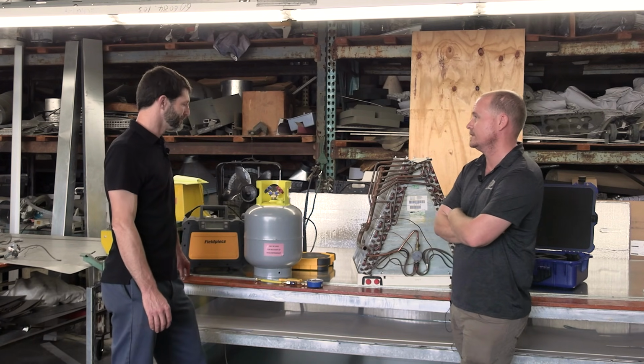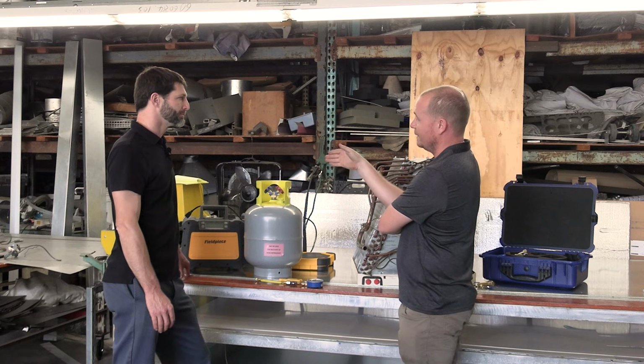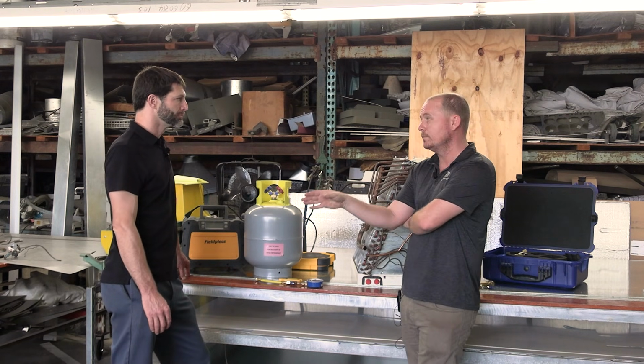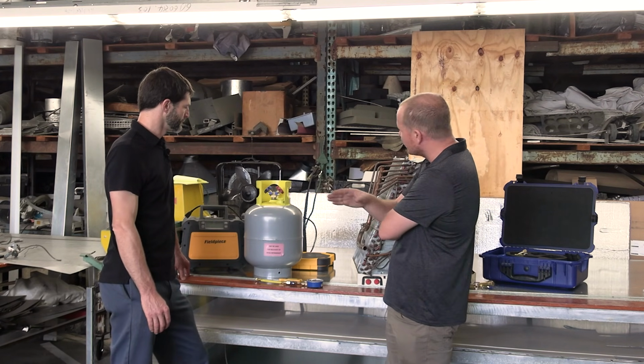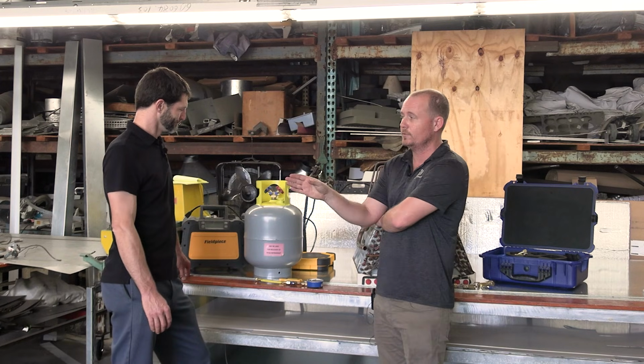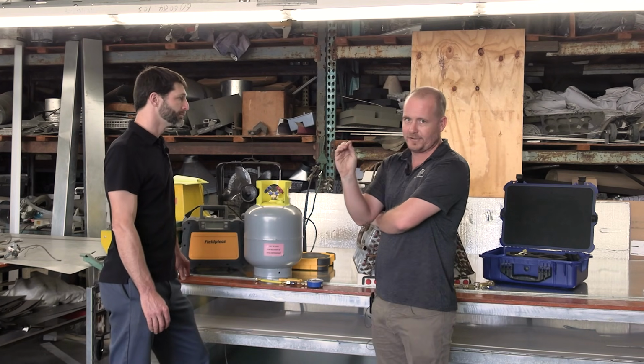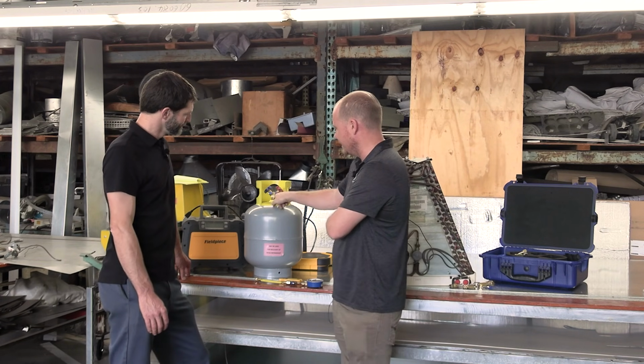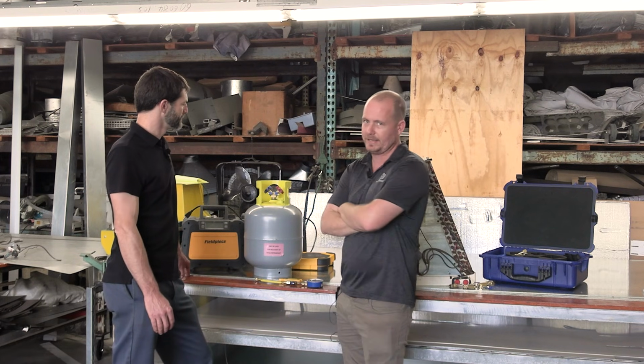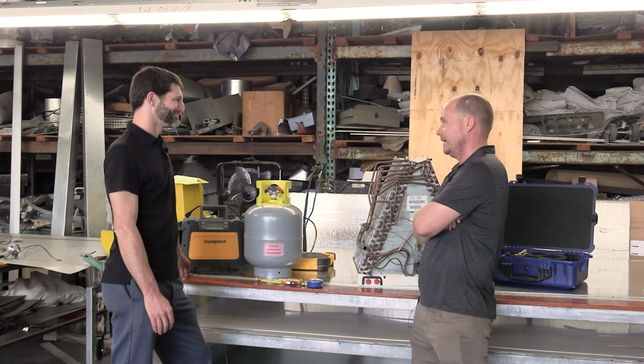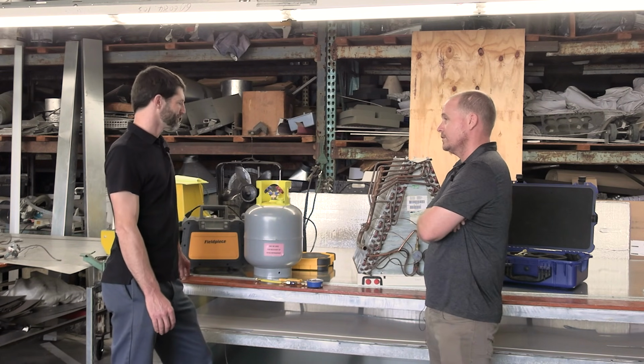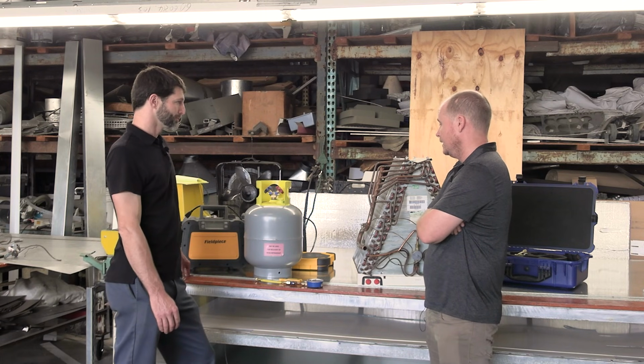And also, I really liked your tip on the vacuum right before you're going to use it. That's a really good point. And the reason is that everything leaks under deep vacuum. Right. Deep vacuum, you're dealing with such a fine scale, and all of these threaded connections over time will begin to leak, and you will end up not having as deep of a vacuum before you're ready to put the refrigerant in it. So that's a really, really good tip.